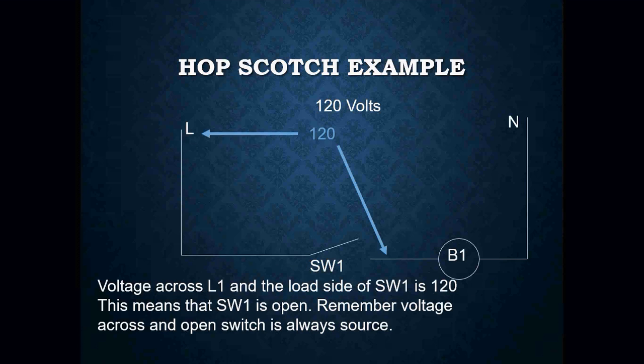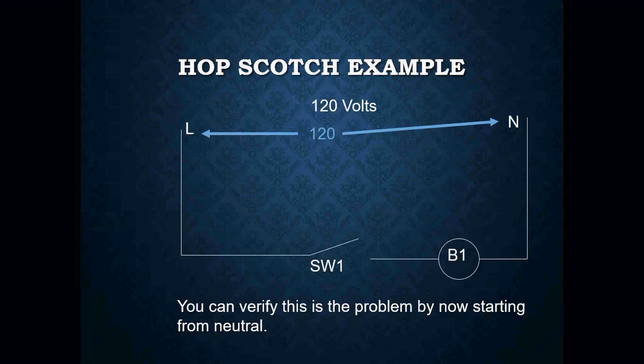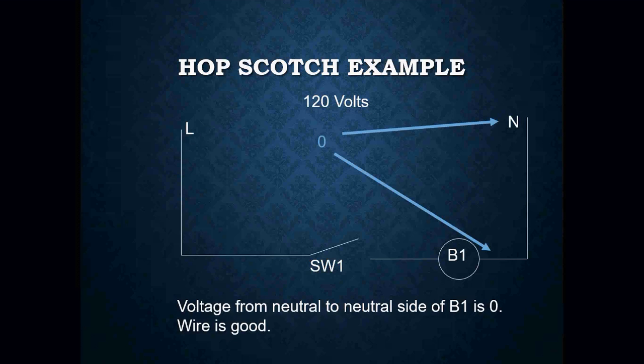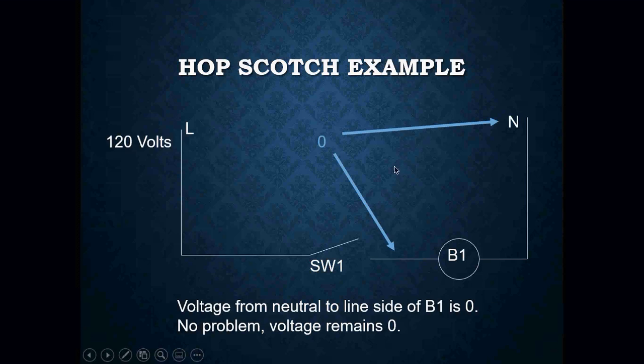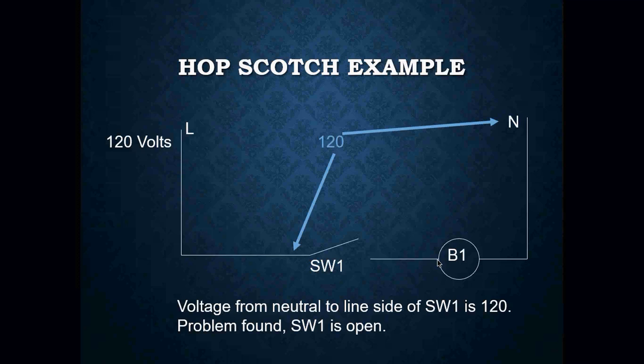We go after the switch, we read 120 volts. Why are we reading 120 volts? Because remember, voltage across an open switch, you will read source voltage. If we go across to neutral, we see that we have 120 volts. Now, we can verify the problem by doing it the opposite way, starting on the neutral side of the circuit. Again, going from neutral to the wire connecting to our load, we read 0. There's no difference in potential. I go across my load to the other side, I'm reading 0. Well, if I'm not reading any voltage here, that's telling me that there is no power being supplied to my load. And if I go across my switch, I read 120 volts. And again, reading 120 volts, that switch is open.